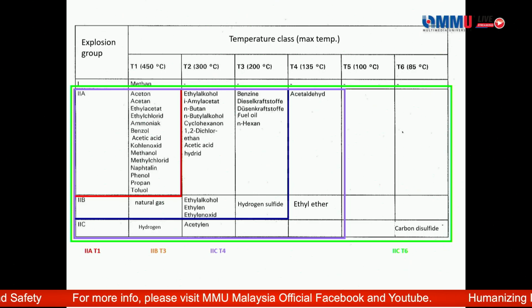flash points, that is the ignition point of different gases. So you can see in this chart, methane, which is so frequently present in the oil and gas industry, is actually the easiest to protect against, because the temperature is quite high under this classification. But what if you have something like carbon disulfide? Then you need a lot more stringent design.